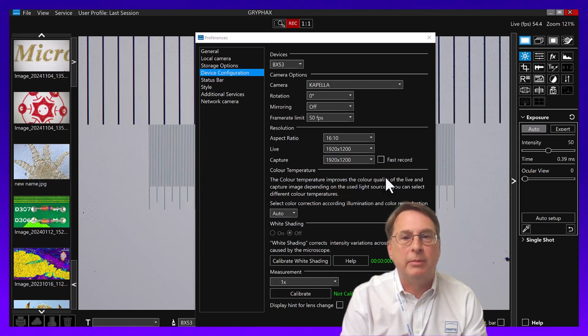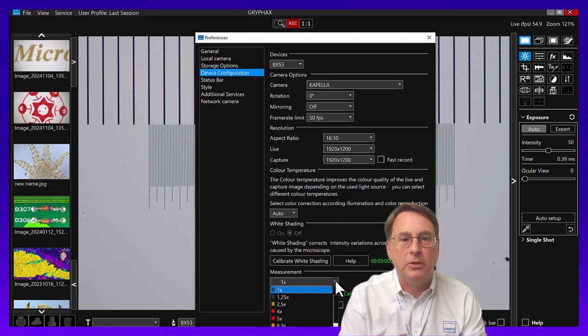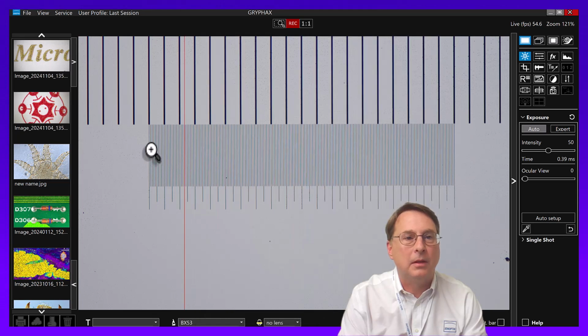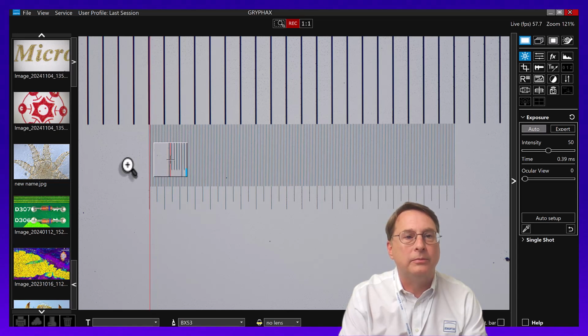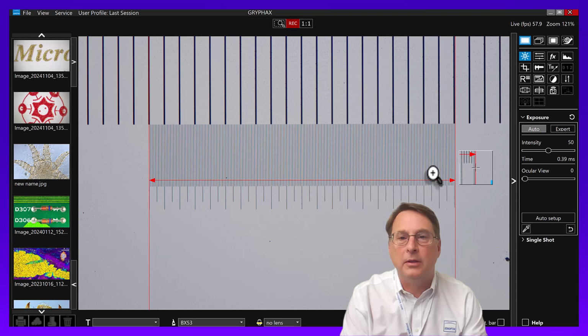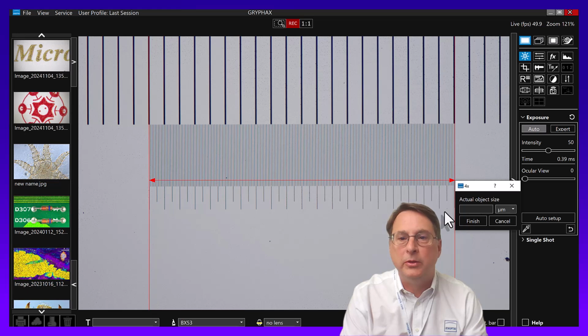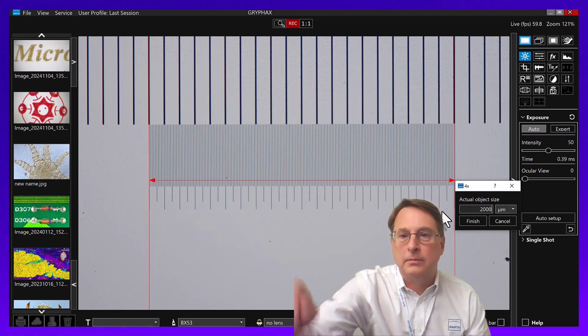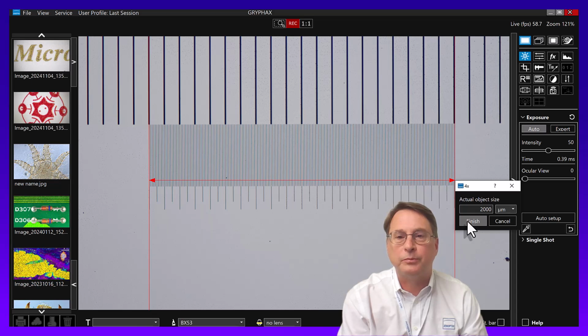So in this scale, the finest increments are 10 micron divisions. This is a 2 millimeter long scale here behind this menu. I'm using a 4x objective to start with, so let me choose 4x here. And then I'm going to click calibrate. And I'll get a vertical line and a little magnifying box that helps me see where I'm putting my cursor. So I'm going to put my cursor right here. And I'm going to drag across, and I'm going to click again on this end. Right there. That is 2 millimeters, so 2000 microns. And then I'm going to click finish.